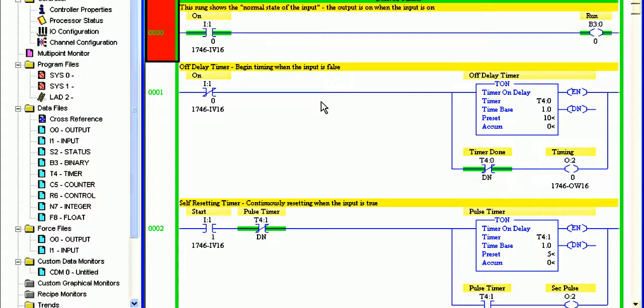I've got a circuit that I've put up here for you to show an example of off delay, and that's just rung zero and rung one. Now with an off delay timer, the timer must begin when the input is off. So that in itself can be a little confusing until you get the hang of it. So if we think about it like turning the switch off, we'll start the timer timing.